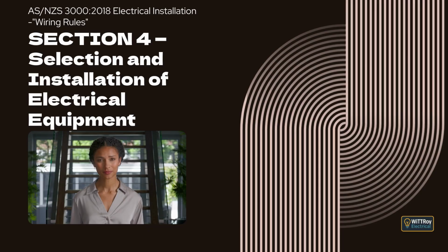Clause 4.2.2.4 Emission of arcs or sparks. This clause explains that where permanently connected electrical equipment could emit arcs or sparks during normal service, it must be fully enclosed in arc-resistant material, or screened from nearby building elements using arc-resistant material, or mounted far enough away to allow arcs or sparks to safely extinguish without causing damage. Clause 4.2.2.5 Electrical equipment enclosures. This clause explains that enclosures must be able to withstand the highest temperatures likely to be produced by the equipment, and that flammable or easily combustible materials must not be used to build those enclosures.